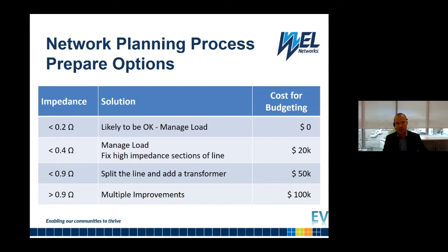So a small cost here for these between 0.2 and 0.4 ohms. But from there, anywhere up to 0.9, we're basically splitting the line and adding a transformer or similar - it's more major. In this case I've used 0.9 because if I have one transformer feeding from the end, and I split at a third and put a transformer halfway between the next two-thirds, I get about 0.3 ohms, and I think I can manage - I'm back into the management zone.